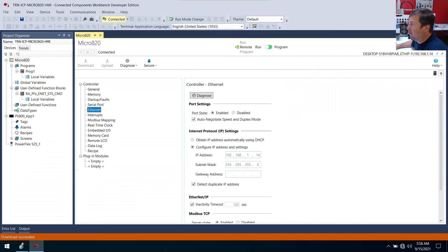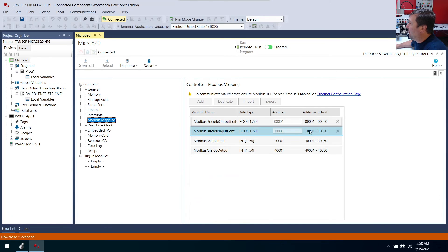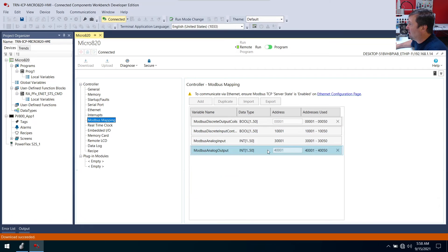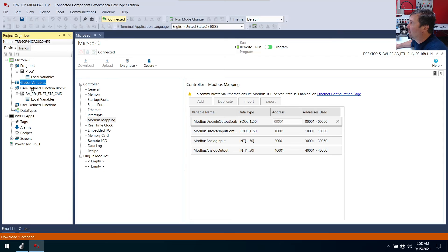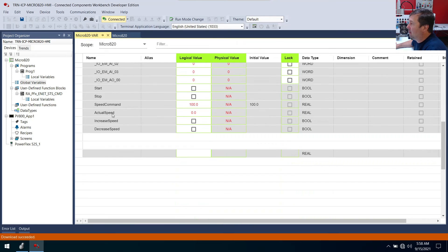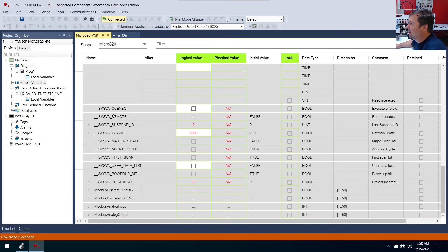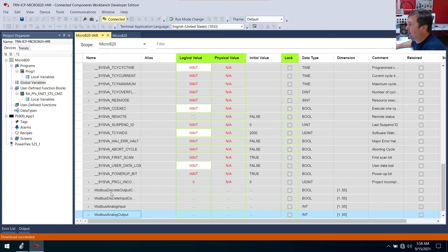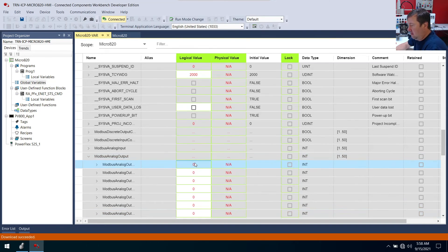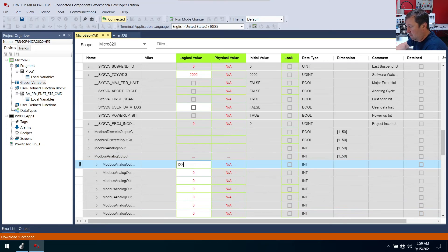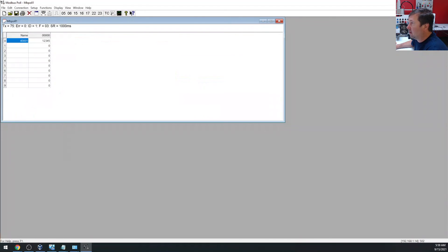And we're going to look at 40,001. Now over here in CCW, we have 40,001 mapped to modbus analog output. And it'll be number one. Now let's go to our global variables. And let's find modbus analog output. And we'll open it up. And we're going to look at value number one. And let's put a value in. One, two, three, four, five.